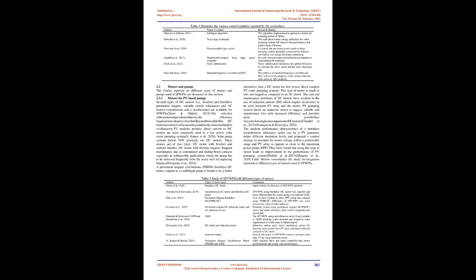Solar water pump. Solar water pumping is based on PV technology that converts sunlight into electricity to pump water. The PV panels are connected to a motor, DC or AC, which converts electrical energy supplied by the PV panel into mechanical energy which is converted to hydraulic energy by the pump. The capacity of a solar pumping system to pump water is a function of three main variables: pressure, flow, and power to the pump. For design purposes, pressure can be regarded as the work done by a pump to lift a certain amount of water up to the storage tank. The elevation difference between the water source and storage tank determines the work a pump has to do.